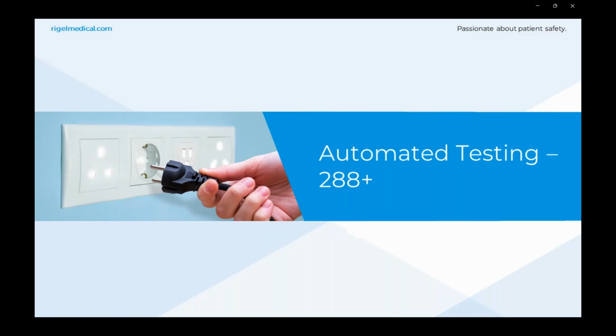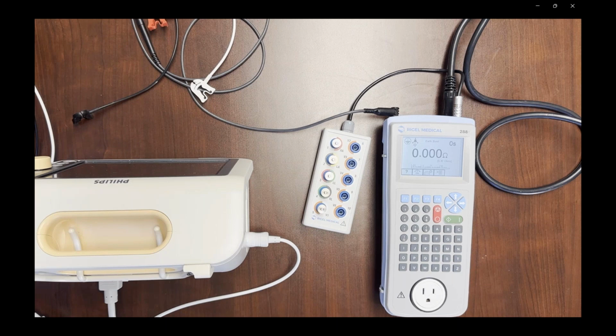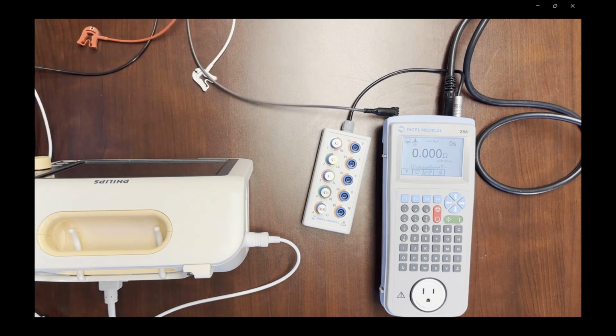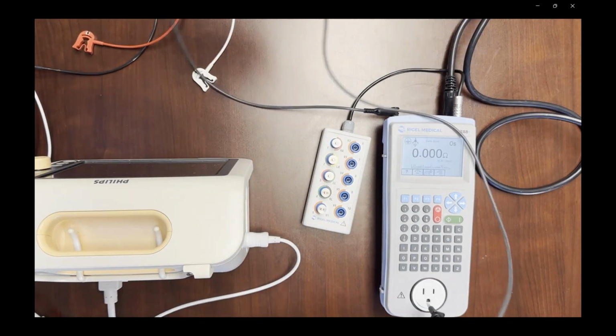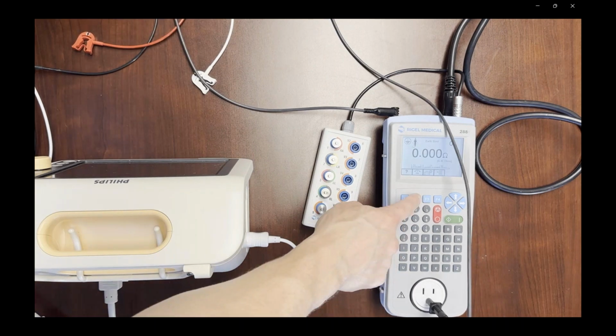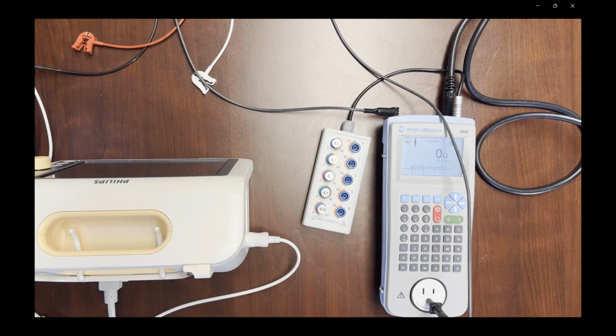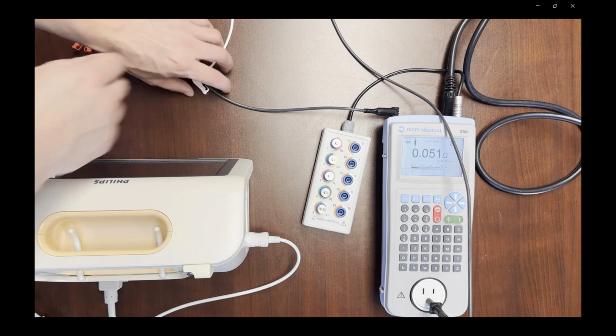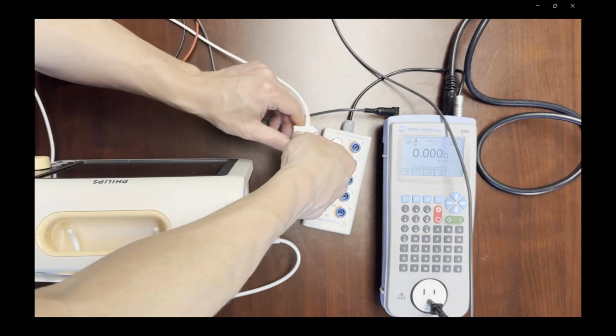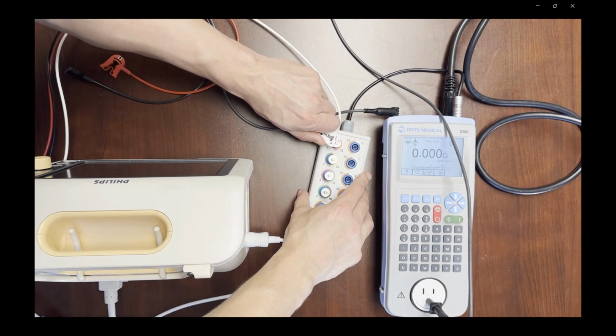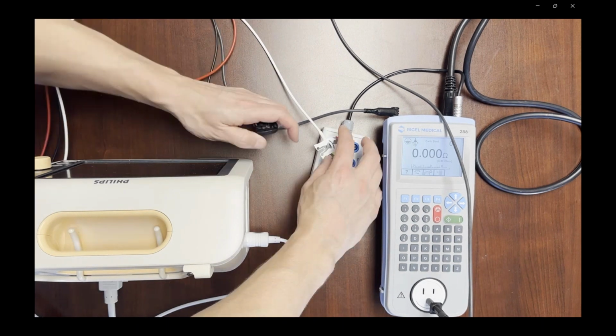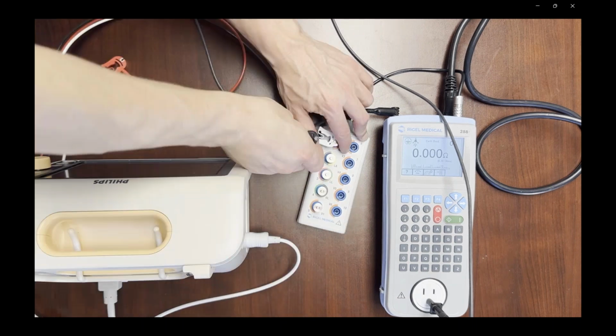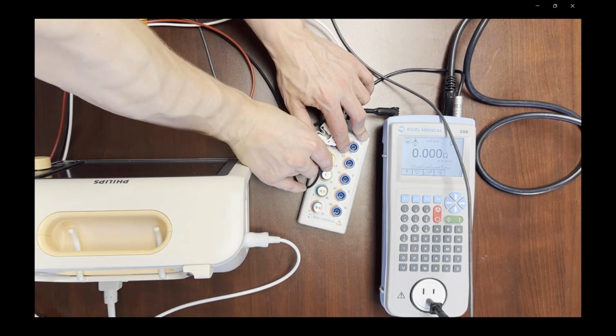Rather than set the device up for a test, I'm going to run through a quick video of the 288 testing to NFPA 99 with a patient monitor and how it's connected. So the ground bond is connected to the device under test conductive part. This ECG connect box has got 5 of those snap connectors already connected. Connect up those ECG leads to there, and then have the ground bond connected to the back. And from there, we can run through an automated test.